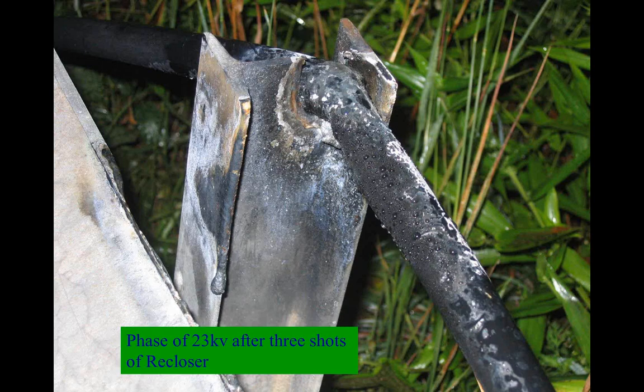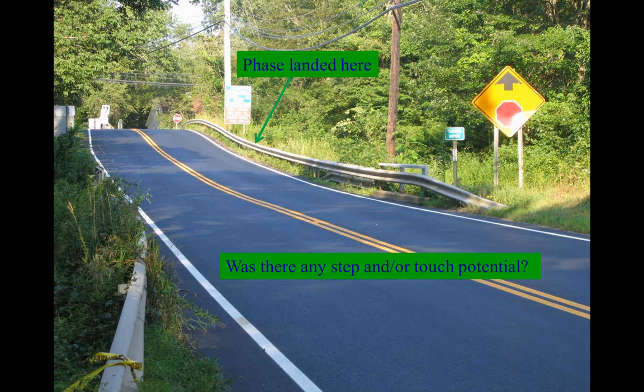Just to show you something, remember that recloser I talked about? It went three shots and locked out. That doesn't go quick. That takes a little time. That's how far it melted into that guardrail I-beam post, steel I-beam. And for a period of time, that whole guardrail from up the stop sign down to the sign was energized at 23,000 volts. Was there any step potential and touch potential? You bet there was. There's a huge amount in that.